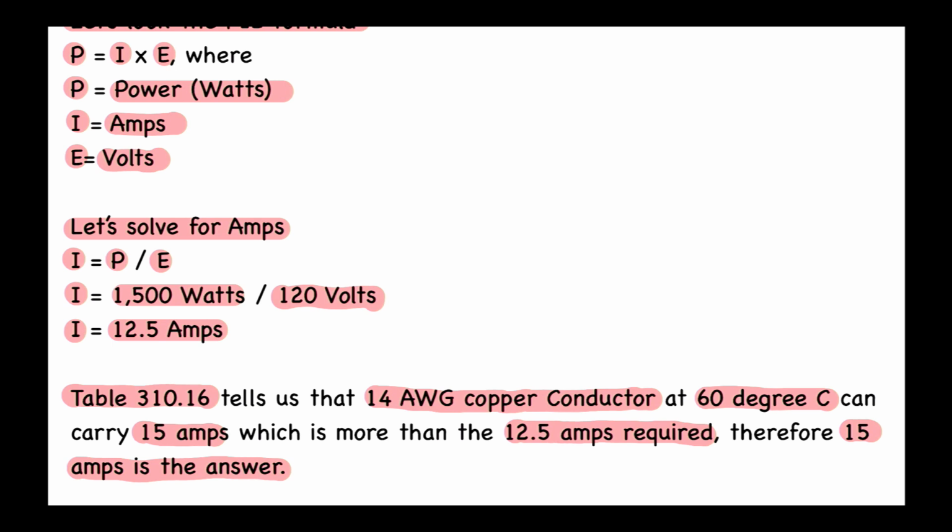There are some electrical contractors that will do the majority of the wiring in a dwelling unit with 12-2. They won't use 14-2 NM for branch circuits, which are rated for 15 amps. They just like using 12-2. And if we look at Table 310.16 in the 60-degree C column, we're going to see that's good for 20 amps for 12-2. Depending on your budget and what you're used to doing, you certainly have a preference, but you cannot go below the minimum standard set by the NEC.